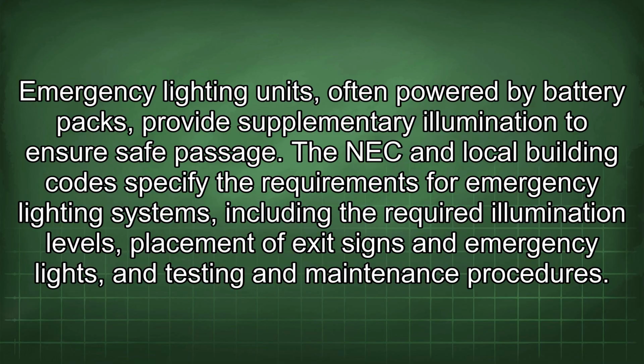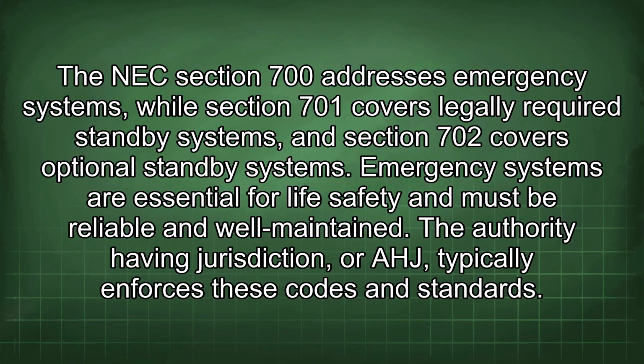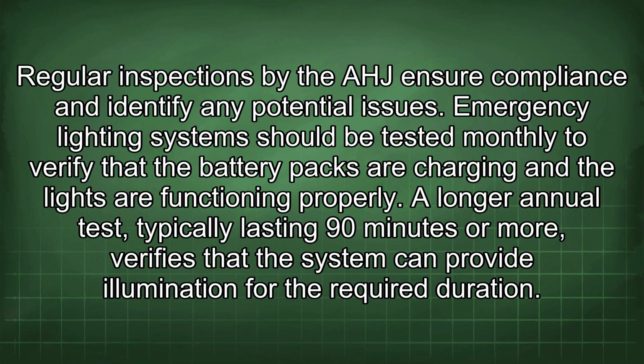The NEC and local building codes specify the requirements for emergency lighting systems, including the required illumination levels, placement of exit signs and emergency lights, and testing and maintenance procedures. The NEC Section 700 addresses emergency systems, while Section 701 covers legally required standby systems, and Section 702 covers optional standby systems. Emergency systems are essential for life safety and must be reliable and well maintained. The authority having jurisdiction, or AHJ, typically enforces these codes and standards. Regular inspections by the AHJ ensure compliance and identify any potential issues.